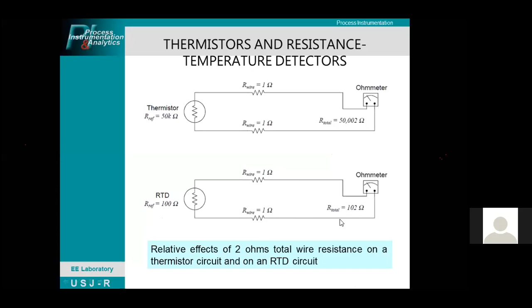With thermistors, this 2 ohms doesn't affect the reading, because of the high reference resistance of the thermistor. Compared to the RTD, which has only a small resistance of 100 ohms, the 2 ohms of the conductor will also affect it. 102 versus 50,002. So the 1 ohm or 2 ohm resistance of the conductor doesn't affect the thermistor much, but it will affect the RTD because of its small reference resistance. Okay.